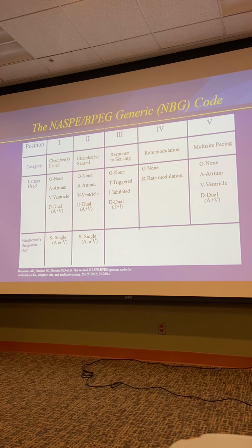That top one, you don't have to worry about. The rate when a magnet's applied depends upon the remaining life in the battery. We just talked about that. For the St. Jude or Abbott devices, which are about 95% of what we put in here, the normal pacemaker rate when you apply a magnet is 98.6 beats per minute. You can't program that in. And when the battery runs down, it goes to 86.3. So if you see those kinds of rates, you know that either a magnet's been applied or the battery's running down.